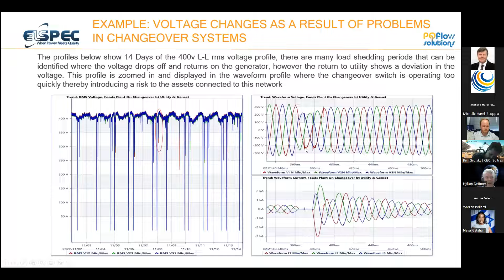Another one that we've had, and is a very well documented case, is where one of the engineers in Eskom logged and put one of the Elspec instruments in on a high voltage network on a large farm. And the background to his investigation was that the standard NRS 048 power quality instrumentation that he had in the network was not showing him what the problem was. It was not giving him the ability to identify the source of the issue.